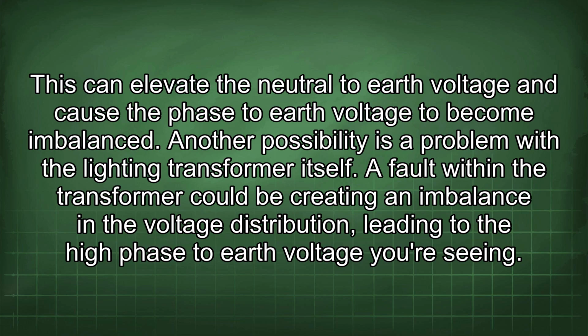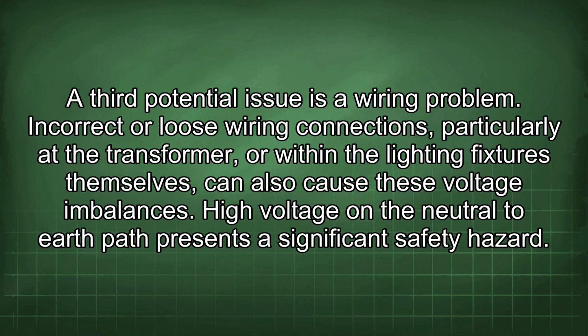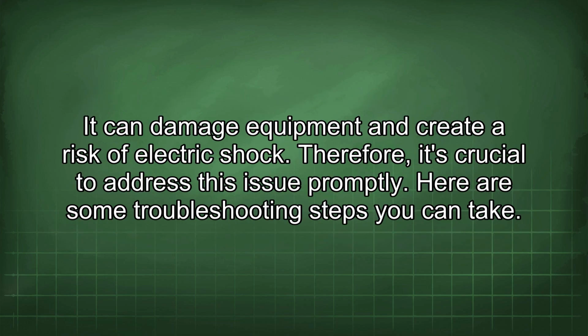Another possibility is a problem with the lighting transformer itself. A fault within the transformer could be creating an imbalance in the voltage distribution, leading to the high phase to earth voltage you're seeing. A third potential issue is a wiring problem. Incorrect or loose wiring connections, particularly at the transformer or within the lighting fixtures themselves, can also cause these voltage imbalances. High voltage on the neutral to earth path presents a significant safety hazard. It can damage equipment and create a risk of electric shock. Therefore, it's crucial to address this issue promptly.